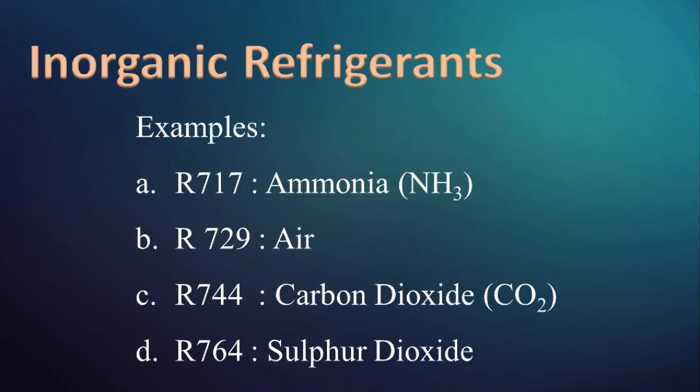Inorganic refrigerants are conventional refrigerants like ammonia, air, carbon dioxide, and sulfur dioxide. These refrigerants are designated by the R7 series. For example, R717 is ammonia. Here R7 is followed by the molecular mass of the refrigerant. For ammonia, molecular mass is 17.